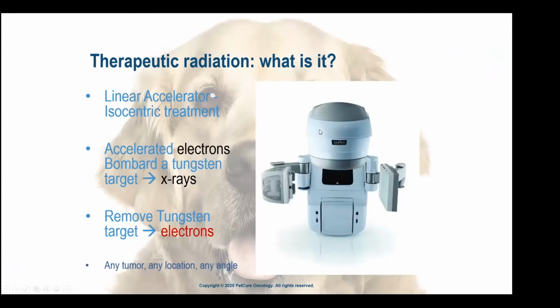So what is the machine? Basically it is a high-powered X-ray tube. We are using electrons from the back of the machine from a tungsten filament. It bombards a tungsten target, and we produce X-rays or photons. Those are what we're using to create that double-strand break interaction in the patient's tissues and the tumor.